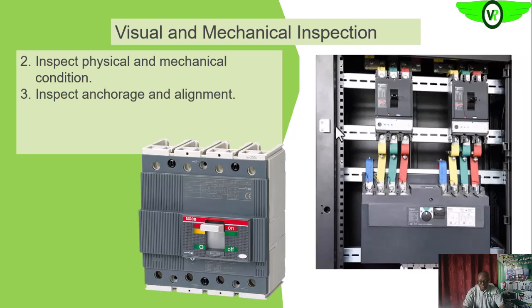We also want to inspect the anchorage to see that the circuit breaker is properly installed. Whether it's mounted on a wall or on the floor, the anchorage should be firm so the circuit breaker doesn't get displaced from its normal position during normal operation.